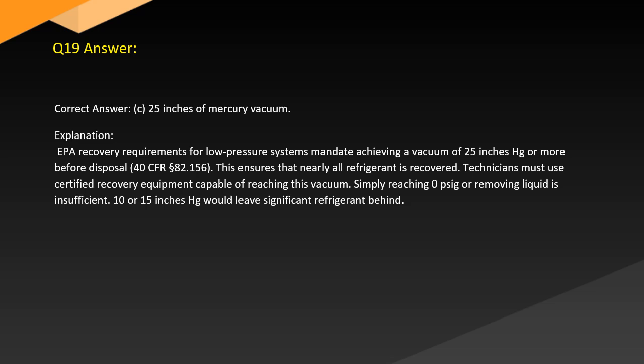Answer. Correct answer, C. 25 inches of mercury vacuum. Explanation. EPA recovery requirements for low-pressure systems mandate achieving a vacuum of 25 inches Hg or more before disposal, 40 CFR 82.156. This ensures that nearly all refrigerant is recovered. Technicians must use certified recovery equipment capable of reaching this vacuum. Simply reaching 0 psig or removing liquid is insufficient. 10 or 15 inches Hg would leave significant refrigerant behind.